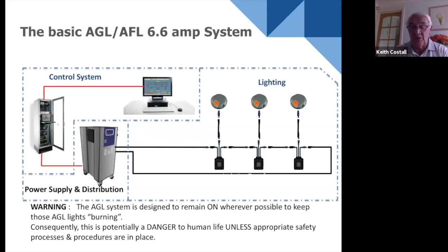So what have we got? The 3 blocks of AGL: the distribution system, the lighting, and the control system, controlling the CCRs, which puts the constant current supply out to the light fixtures. So there's just a list of what we have. Primary circuit, the CCR, lightning arresters. Not all manufacturers and CCRs offer you lightning arresters. So be aware. A lightning arrester is there so that in the event of an indirect lightning strike, where a voltage gets induced into the primary cable, it could go back into the CCR and burn out the electronics in the CCR. So the lightning arrester is a safeguard to minimize that effect if that happens.